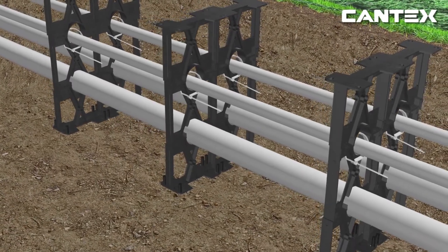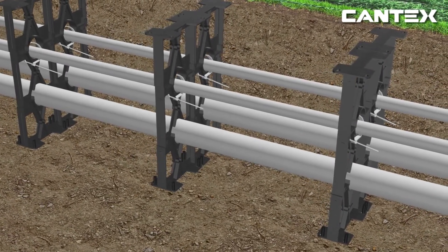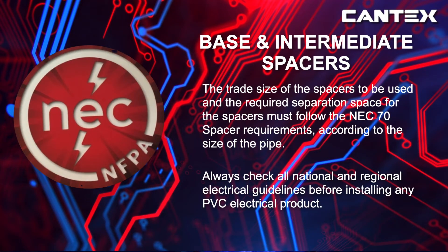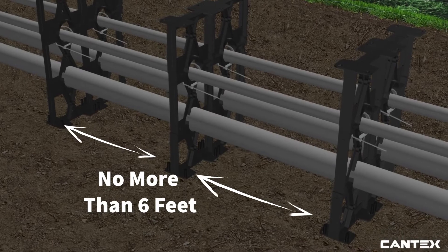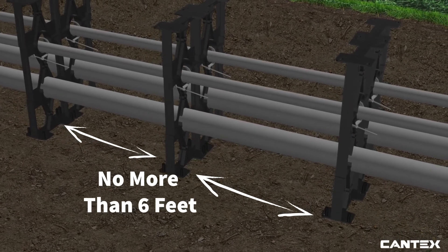For example, a ½ to 2-inch pipe must be spaced 3 feet or less. If you are running two different sizes of PVC pipe, use the larger size spacer required for the large pipe and use cable ties to secure the smaller pipe to keep it from moving during concrete pouring. Make sure to refer to the NEC 70 spacer requirement chart and use the spacer requirement for the smaller pipe. You can see here that the smaller 3-inch pipe has been tied down with cable ties and that the space between spacer sections is no more than 6 feet, even though the larger pipe allows for greater space.